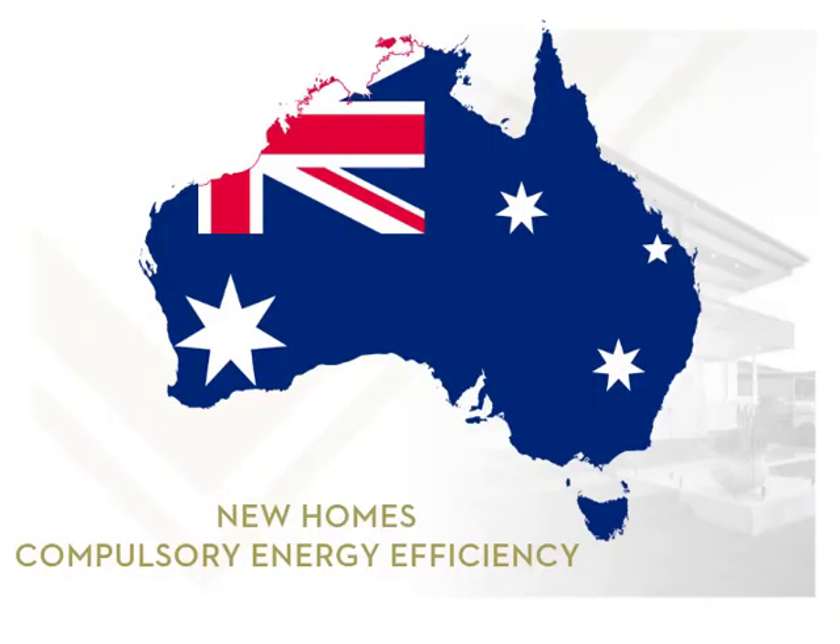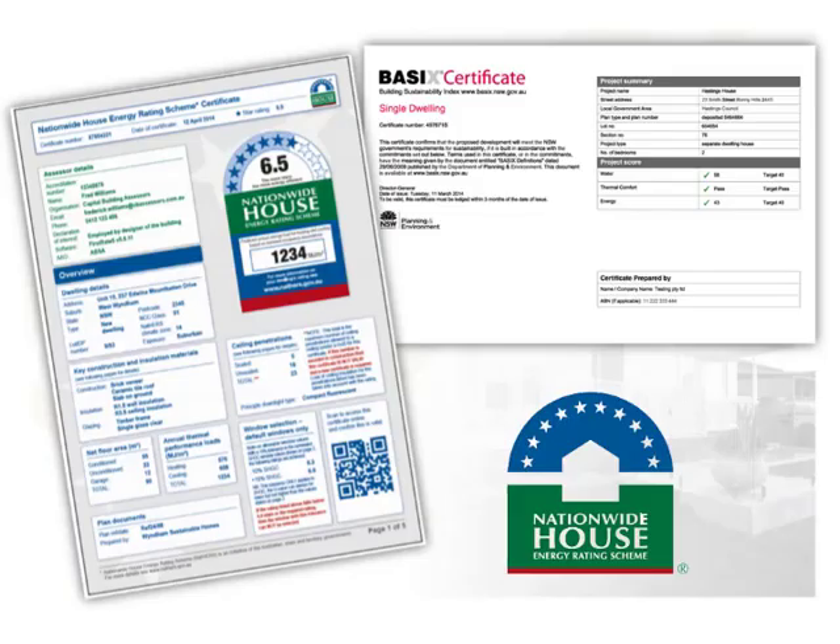Energy efficiency levels for new homes are compulsory all around Australia, and they call for particular energy values for windows. The windows selected must meet the ratings stated in a NatHERS — the Nationwide House Energy Rating Scheme — Energy Report, a BASIX report in NSW, or another approved method. Where there is a range permitted for the ratings, it will be shown on this report.